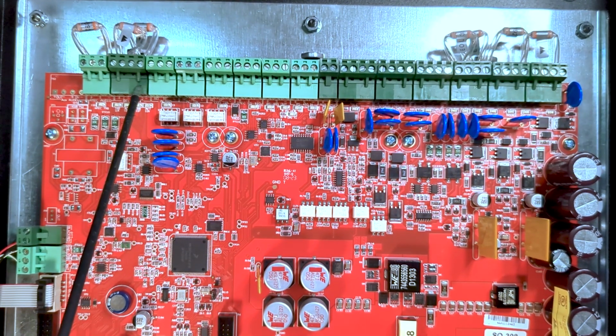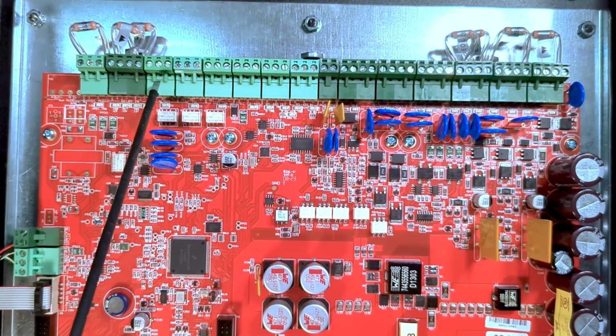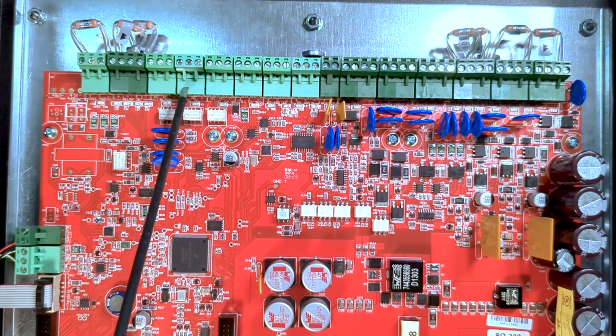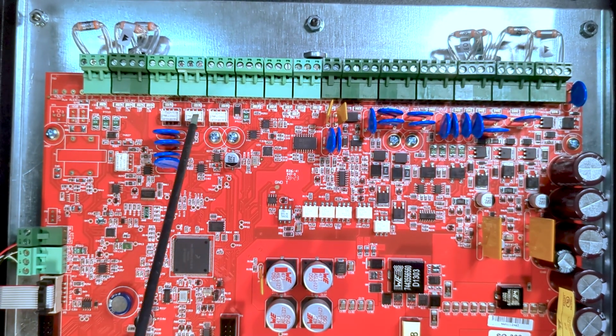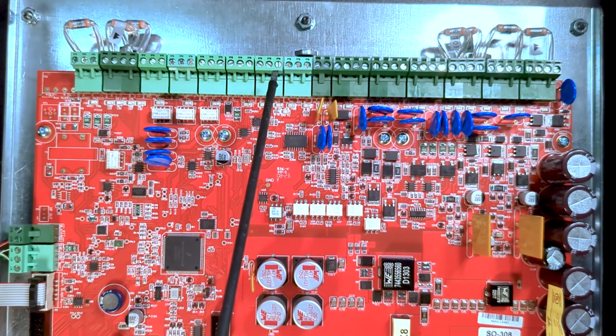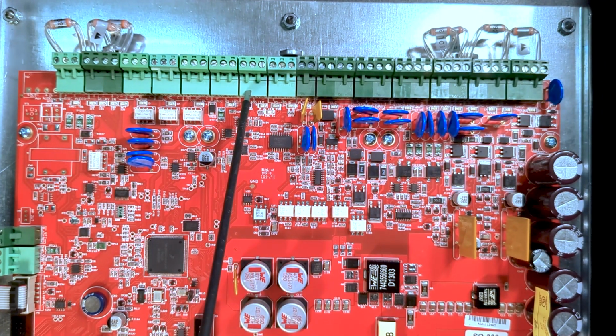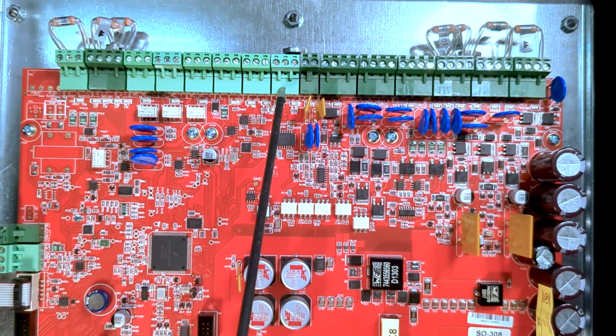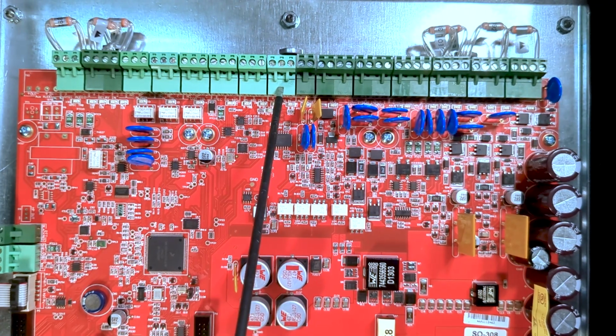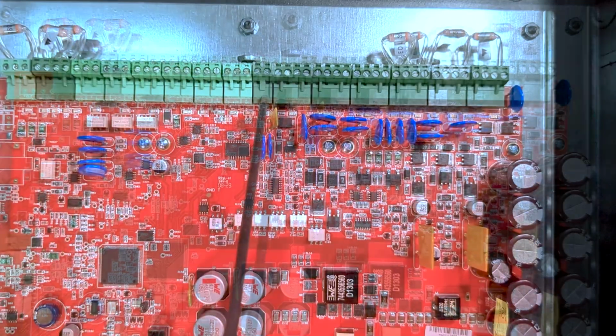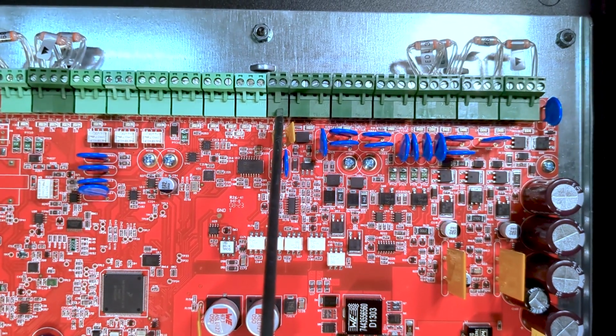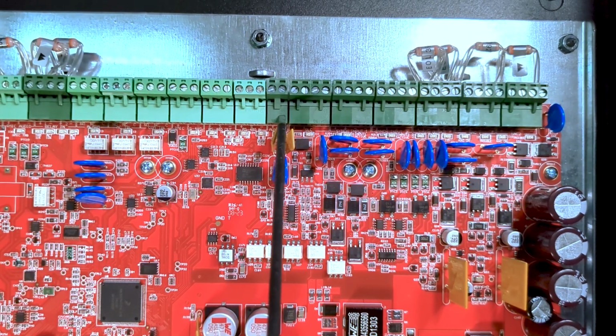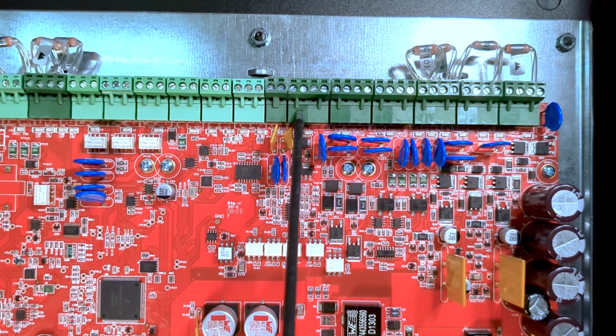We also have two relay inputs, which allow for panel activation, dedicated alarm contact, AC trouble, and common trouble relay contacts. Next, we have the RS485 out and in connections to communicate with subsequent booster panels in Class A or Class B. Moving on, we have the 24-volt aux output, the signaling line circuit connection for compatible fire alarms.